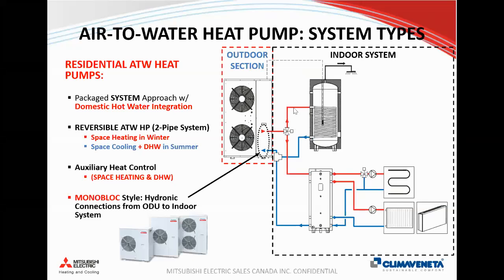So anytime you're looking at a specific heat pump, you need to understand how that machine's going to behave according to outside air temperature. But just very quickly with residential type systems, these are usually packaged systems for residential applications, where it's a little bit of a system approach. So you're able to have space heating and cooling with the appropriate terminal equipment in the building, and also integrate domestic hot water into those systems. So basically in summertime, the heat pump can provide cooling to use with fan coil units inside the house or things like that. And whenever it's met the conditions inside for cooling, it can switch and make hot water to charge a hot water domestic tank.